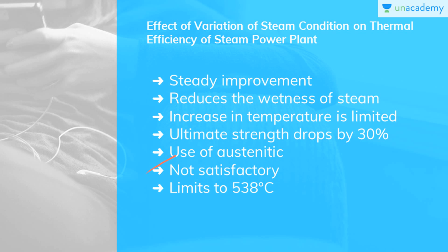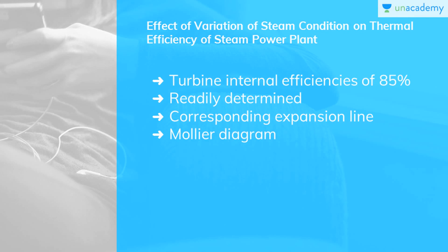Steam temperatures up to 600 degrees centigrade can be used in some power plants. However, operating experience with expensive high-temperature austenitic steel is not always satisfactory. The maximum steam temperatures are generally limited to 538 degrees centigrade and in few cases to 565 degrees centigrade. The maximum steam pressures or throttle pressures can be used at 3 different condenser pressures and 2 inlet steam temperatures.